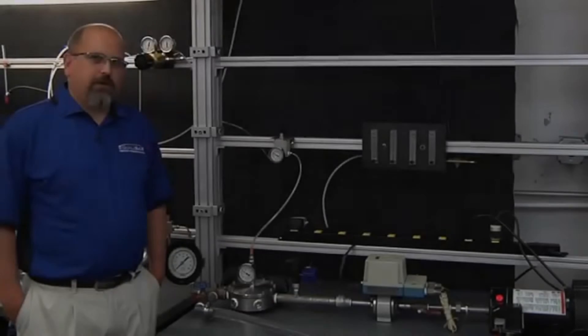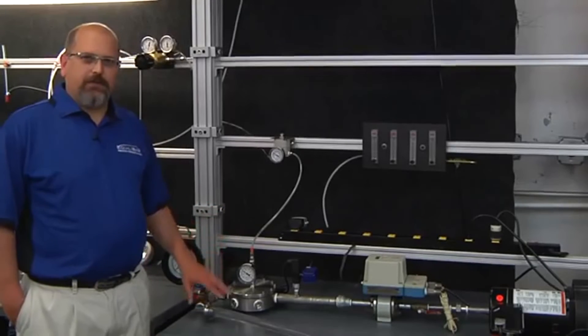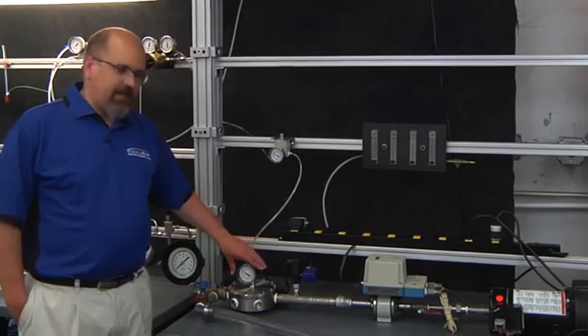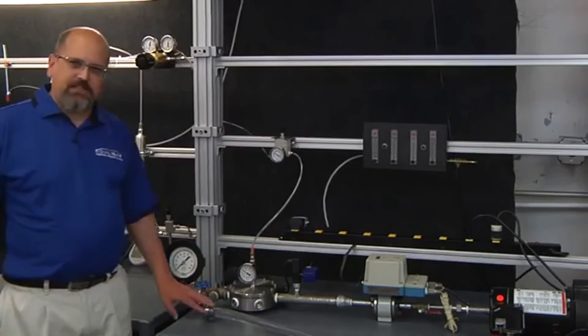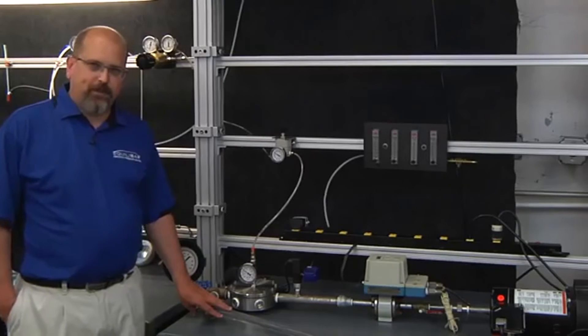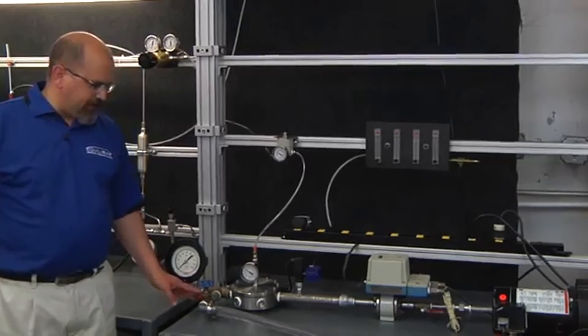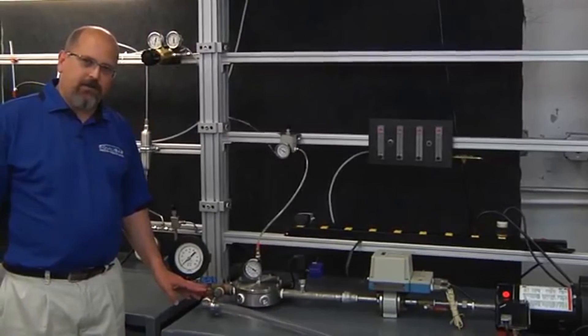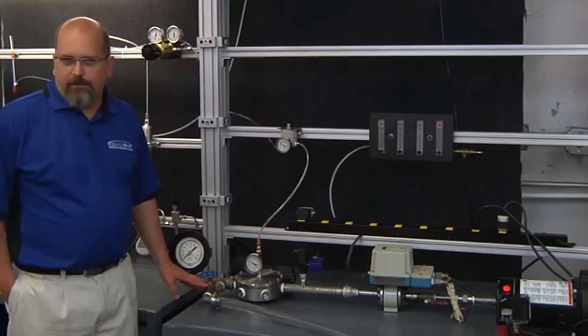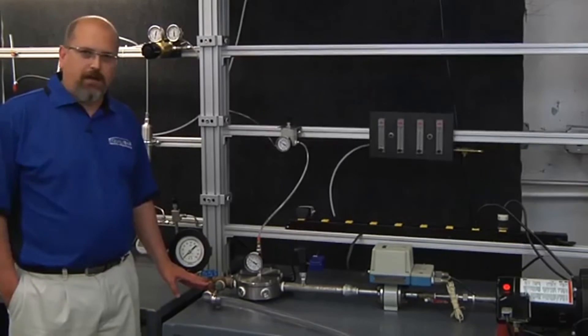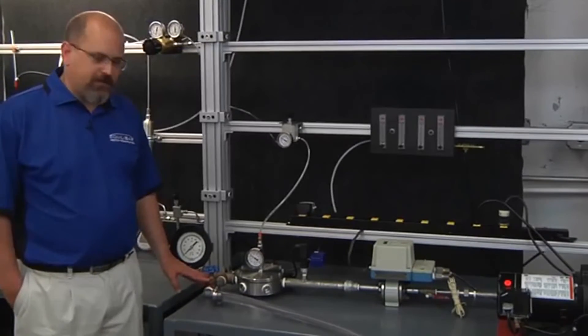For our next test, we're going to demonstrate that the flow rate through the system, once it's set by the Equilibar Back Pressure Regulator, is not affected by changes downstream in the system. I'm going to represent changes in the downstream system by this gate valve. So I'm going to modulate this gate valve, and that's going to represent a filter plugging up, or valves turning on and off, or other demands on the system.